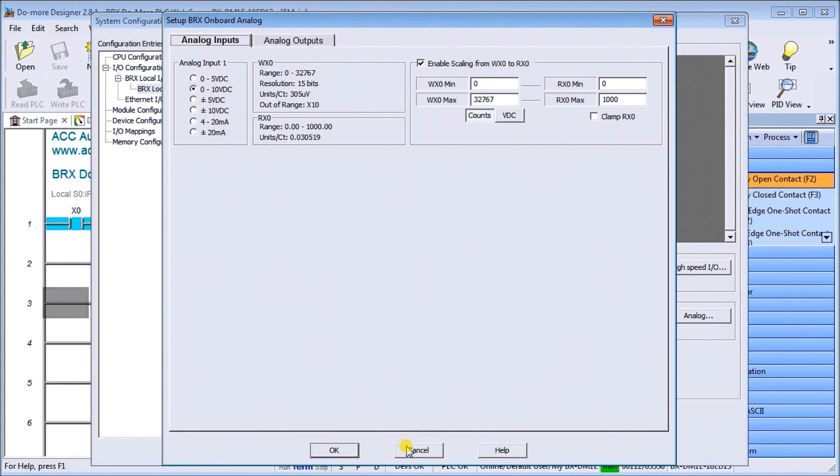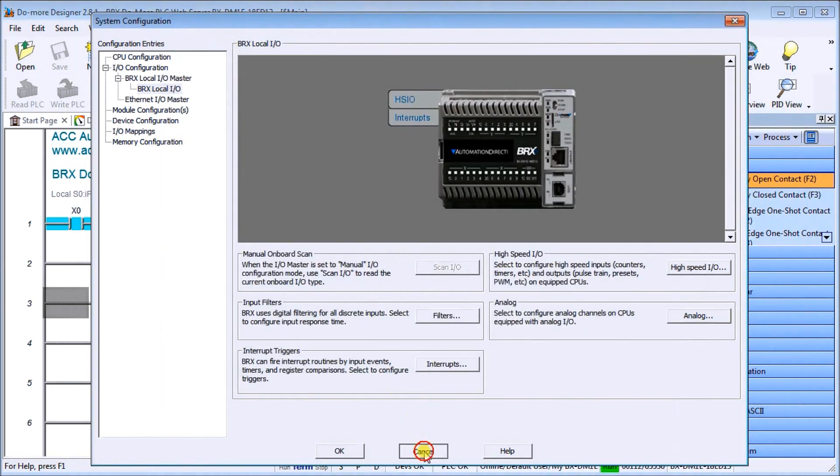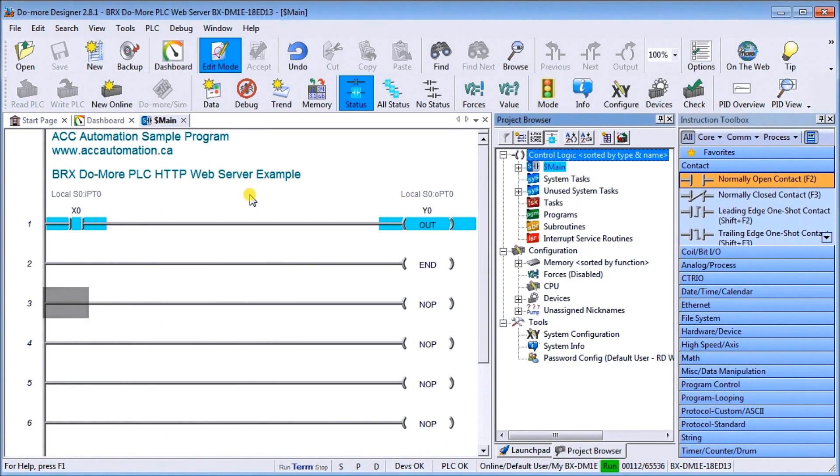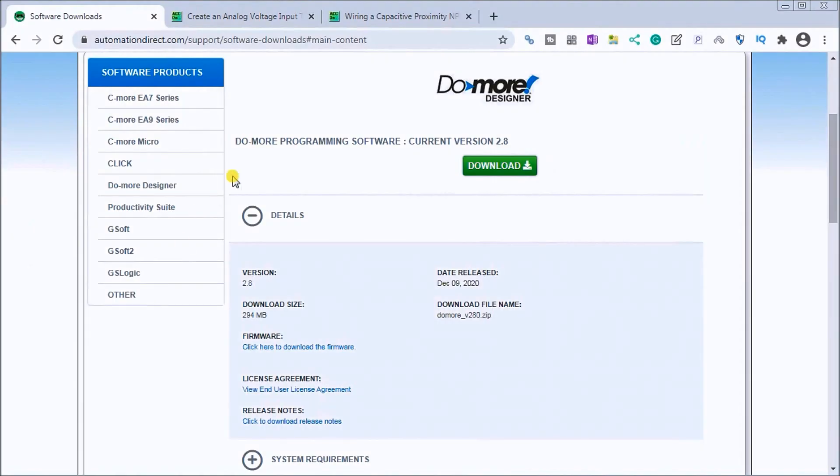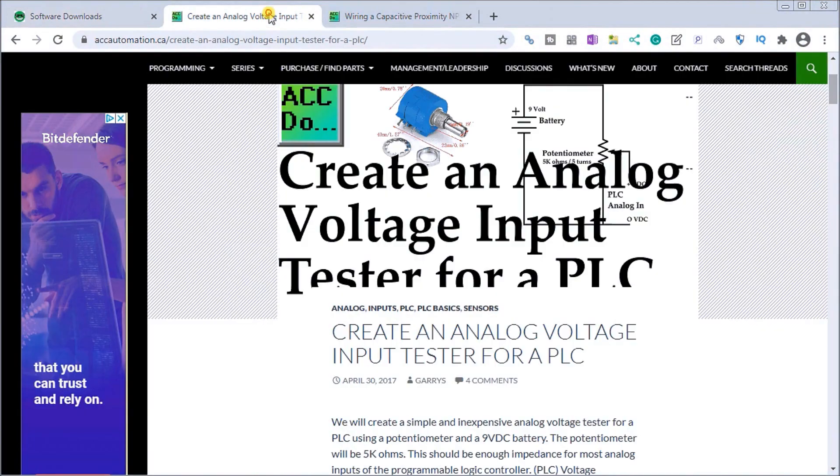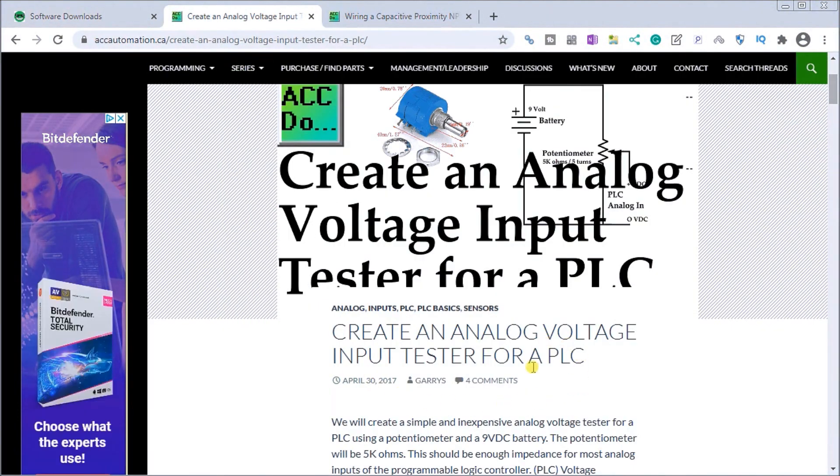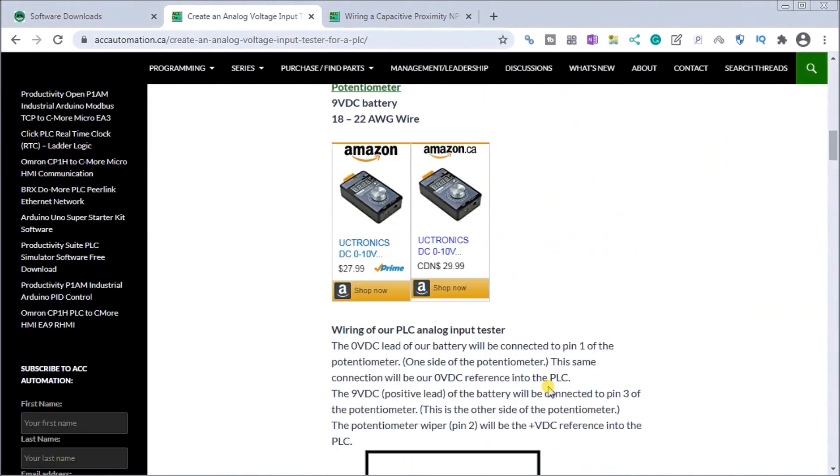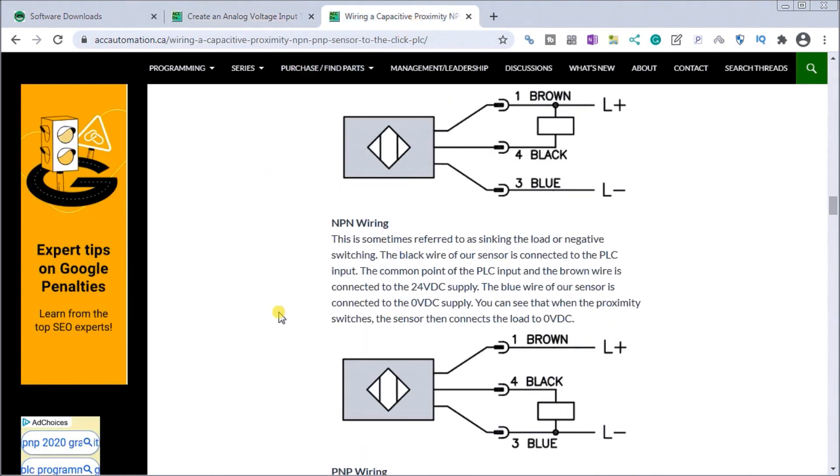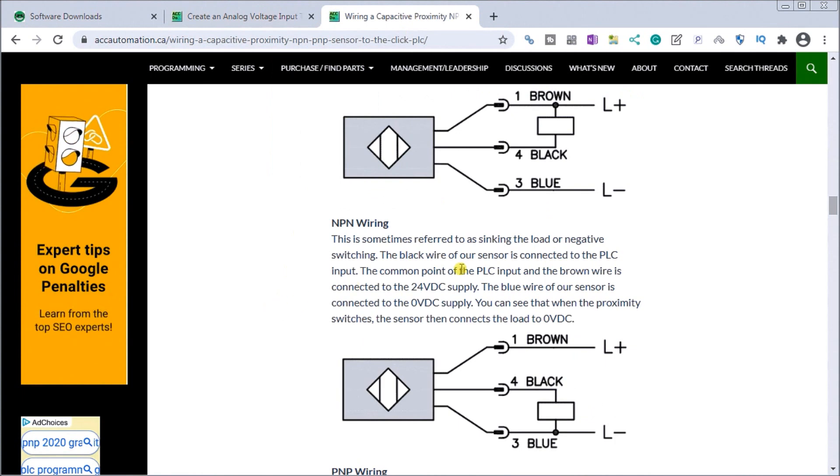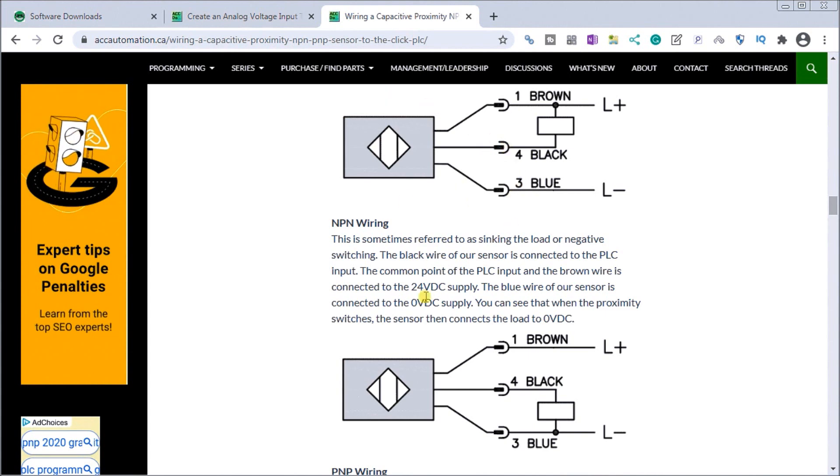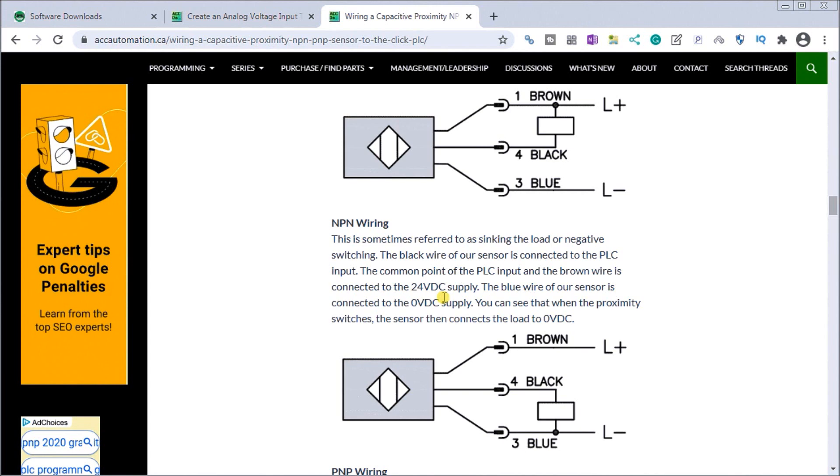That's how we set our analog in. To develop that, we've actually created a website or web thread that tells you how to create this analog input signal. Just a simple 9 volt battery and a potentiometer that will feed in 0 to 9 volts, which is good for testing out this type of thing. We're also going to be wiring in our capacitive type proximity sensor, NPN, and that's going to trigger the first input to the PLC.